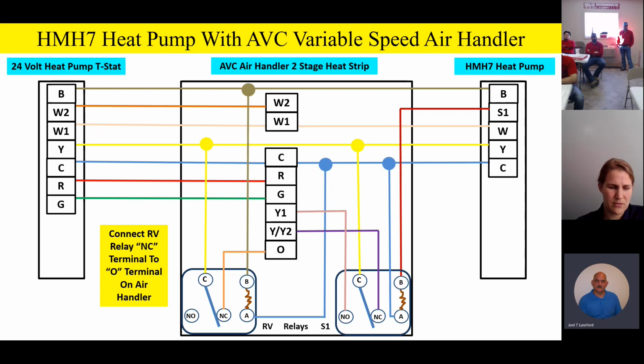Now, guys, the reason we have to do this, just so you know, on the variable speed air handler and the variable speed furnace, the way the board is configured, the actual control board on the furnace or the older style air handler has to see an O signal in the cooling mode for advanced functions. Let me say that one more time. On the variable speed product that we're looking at, it has to see an O terminal in the cooling mode for some advanced dehumidification and some advanced motor ramping functions. So in the cooling mode of operation, right now we're in the cooling mode. If we energized the thermostat right now for compressor operation, we would be in high speed airflow in the cooling mode because we have that O terminal energized on the indoor unit. Any questions or comments so far?